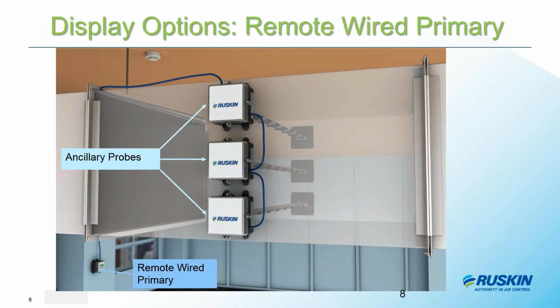What this is showing is our least expensive remote option, which is a remote wired primary. And here we just take the primary, which you previously saw on the end of the probe, we take it off the probe and provide it as a separate part. This remote then allows you to mount the primary, which is shipped separately, up to 500 feet away from the air measurement station. And again, we just use a simple twisted pair to go from the air measurement station to the remote located primary.